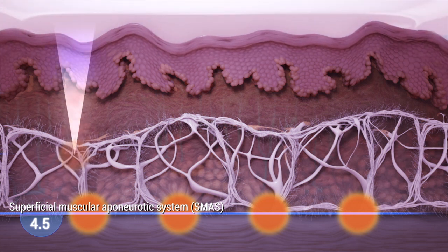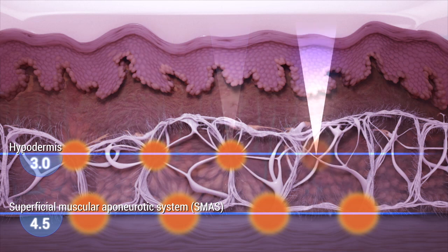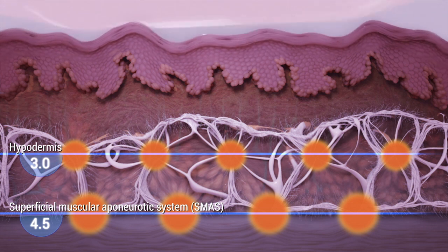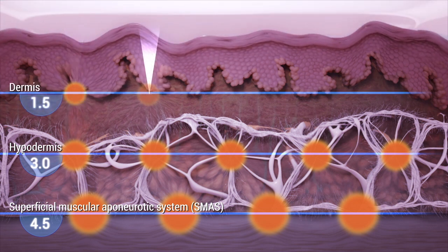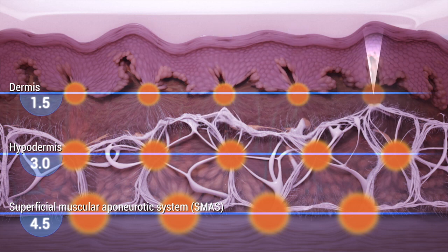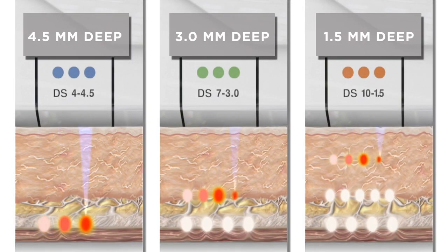During an Ultherapy treatment, ultrasound waves are micro-focused at precise depths in the dermis and hypodermis, sparing the skin surface and intervening tissue. Friction heats the tissue to between 60 and 70 degrees Celsius, forming thermal coagulation points at depths of one and a half, three, or four and a half millimetres.